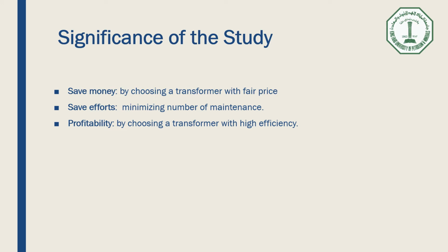Because I will save money and effort for the Saudi Electricity Company by choosing a transformer with fair price and minimizing the maintenance cost by choosing a transformer with high reliability. Reducing the losses on the transformer, I mean power losses, gives us high efficiency, which means higher profitability. An excellent performance of the transformer leads to cost saving and minimizes the maintenance, which will raise the profitability. Operating age is one of the important factors if I want to choose a transformer, because the longer the transformer operates, the more cost saving there will be.